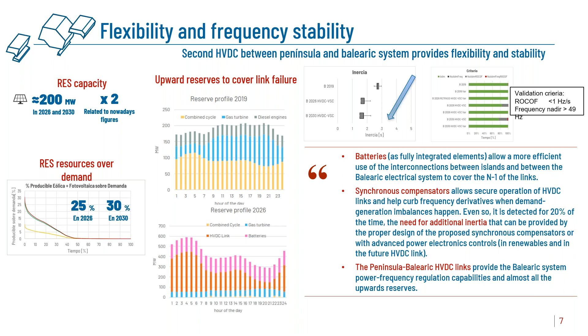In both cases, it means power electronics coming from HVDC or from renewable energy displace synchronous generators, and thus the inertia of the system decreases. So to compensate for the loss of inertia and lower short circuit power, the installation of synchronous compensators is proposed, or is required, in this system in order to ensure the correct operation of the HVDC links. So at the end, the stability of the frequency is supported by the emergency control of the Peninsula Balearic Islands links and batteries. These batteries, as fully integrated elements, are only activated in a standby situation and only when there is an HVDC pole trip or an island AC interconnector trip.